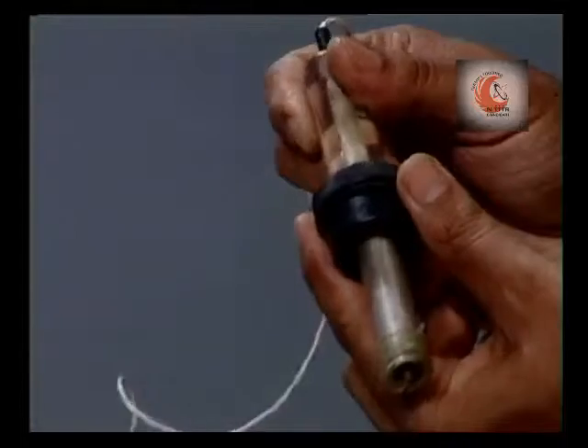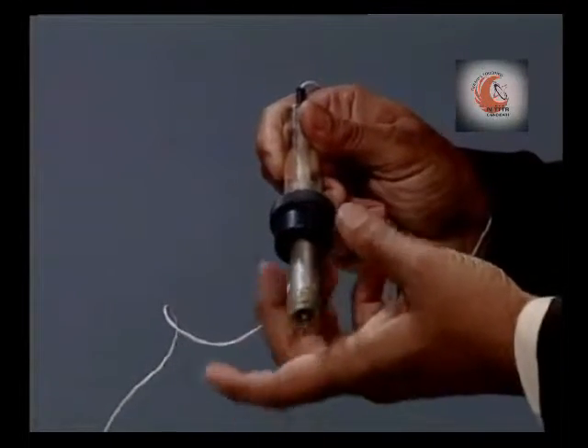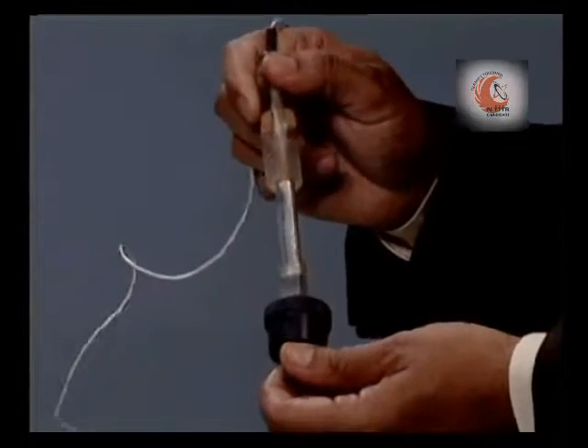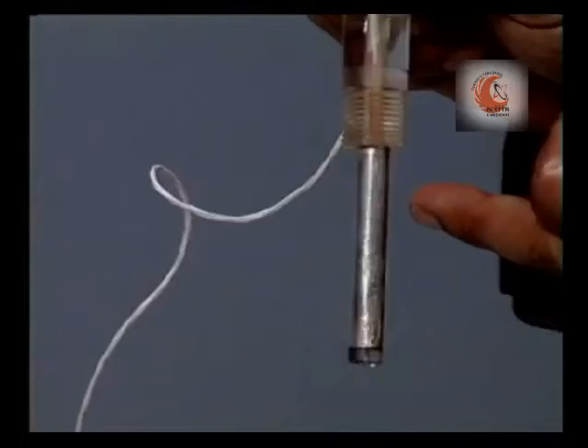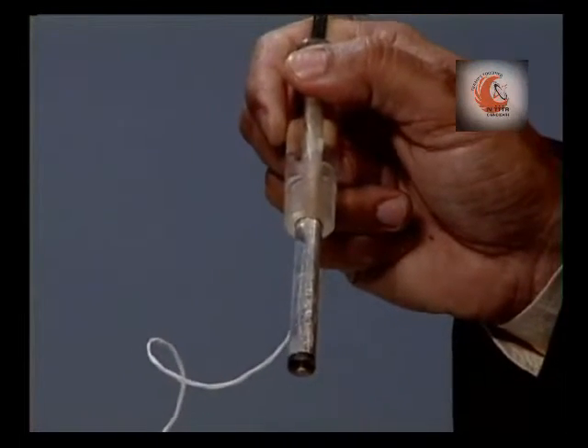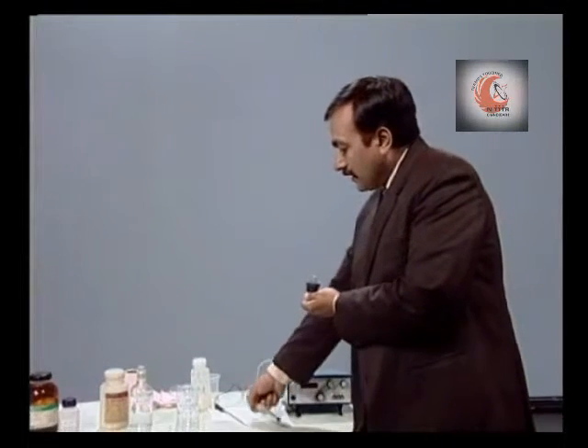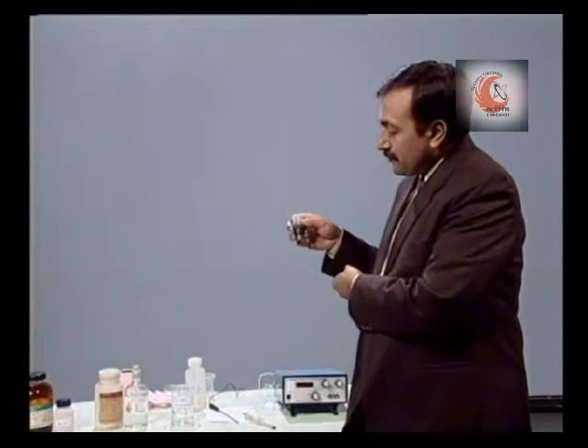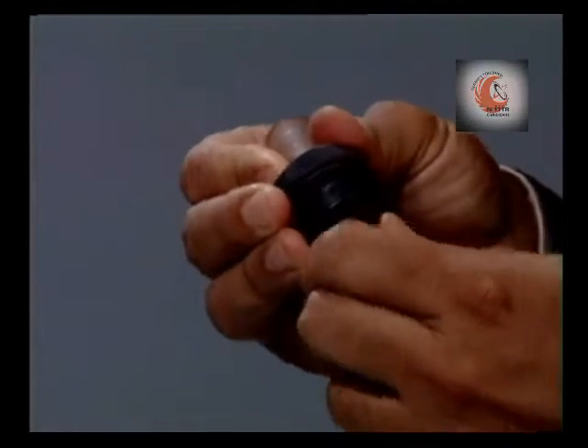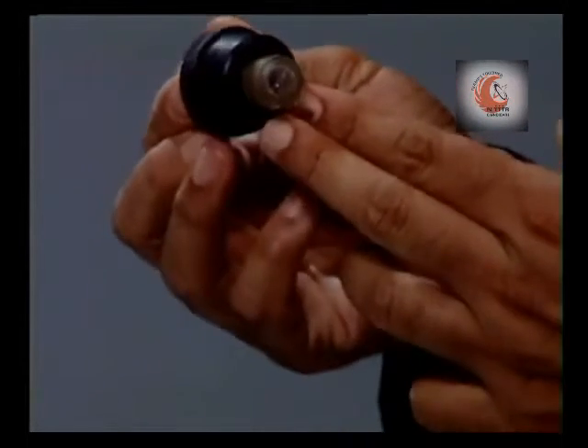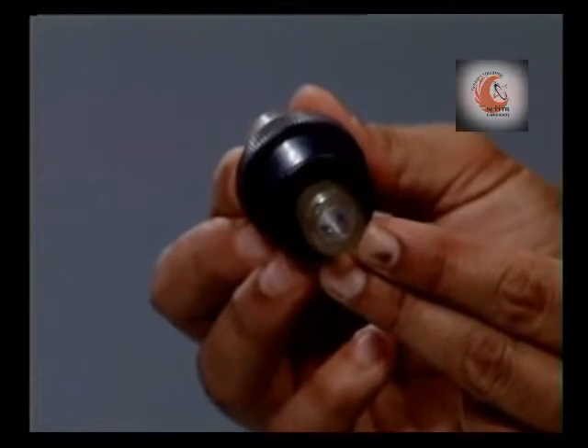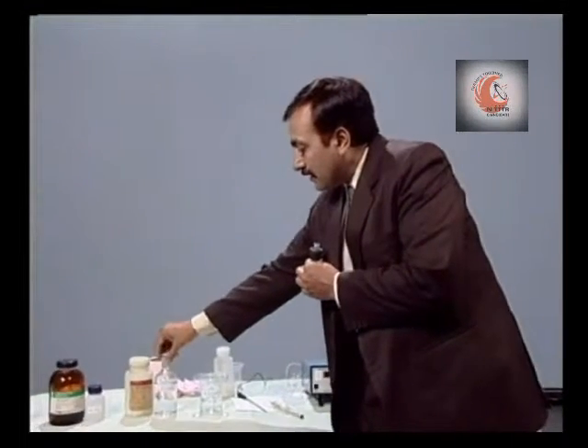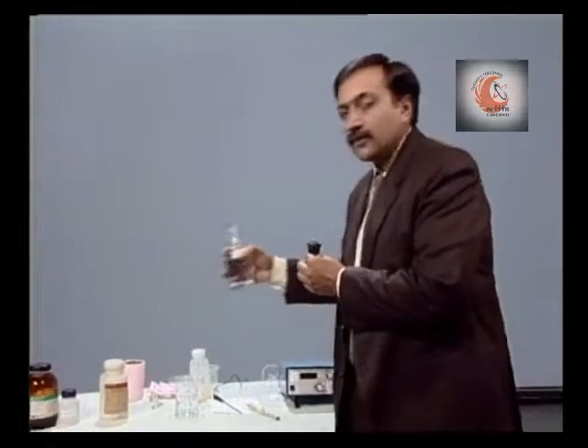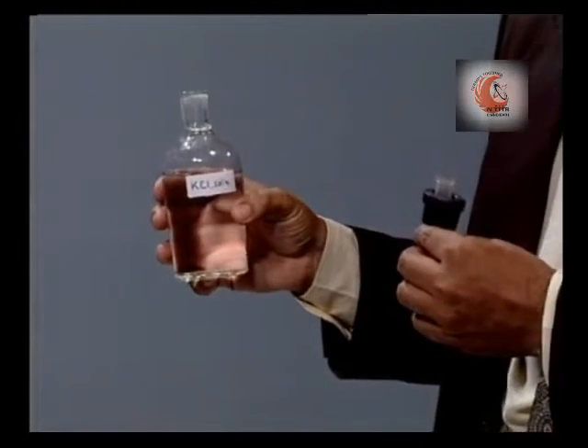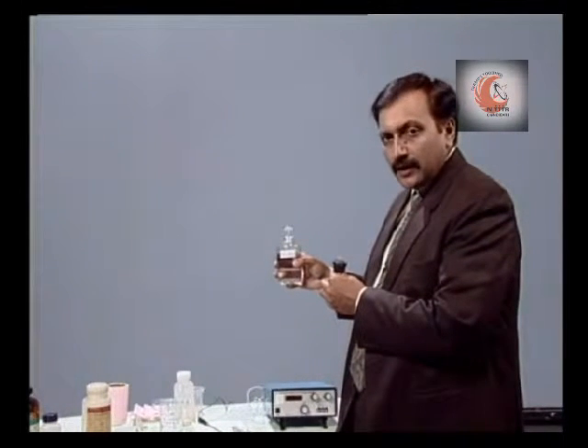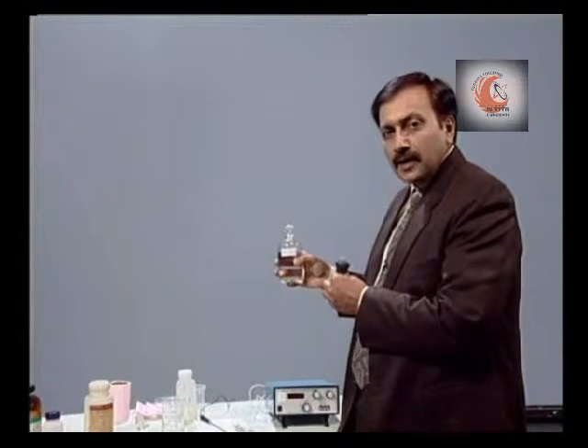To assemble the DO probe, open the cap, now check that the silver anode and the gold cathode are clean and shining. Now we will fill the electrolyte in this tube. First see that the DO membrane is not punctured or torn out. The electrolyte which is used is a KCl solution. Usually a 7.5% solution is recommended as electrolyte. However, we must check up with the recommendations of the manufacturer.